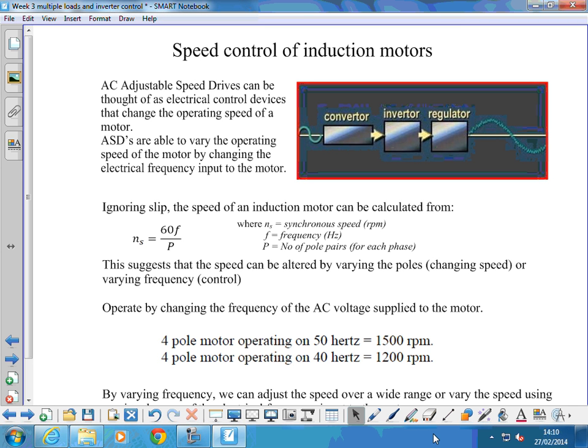If we vary the number of poles, all that really is doing is changing the speed of the motor. We can't really do that dynamically. We can't climb inside the motor while it's going round and stick an extra couple of poles in or take them out. So that's just changing the speed of the motor by changing the number of poles it has. But varying the frequency, we can do dynamically, and therefore that's control. It's not just changing it, it's control, and we can do that as the thing is operating. For example, if we have a 4-pole motor operating at 50 Hertz, we'd get 1500 RPM. If we have a 4-pole motor at 40 Hertz, we get 1200 RPM.